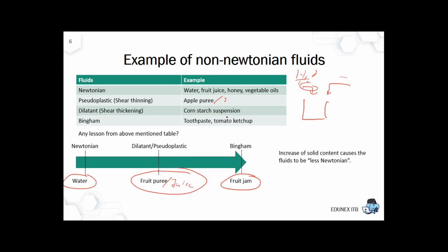No flow can be detected because it cannot be used to flow non-Newtonian fluids, especially Bingham fluids. When you are using Bingham fluids, it's better for you to use a positive displacement pump, a piston pump, because the head is ensured with the piston movement compared to the rotation movement.